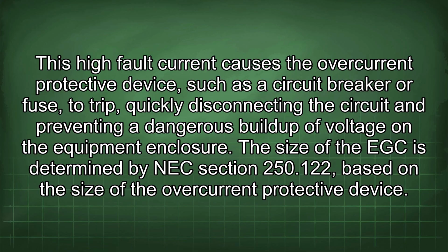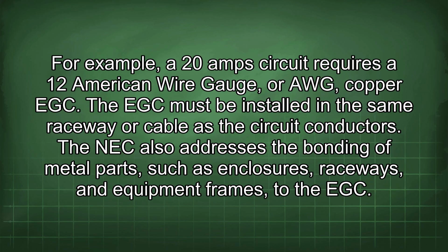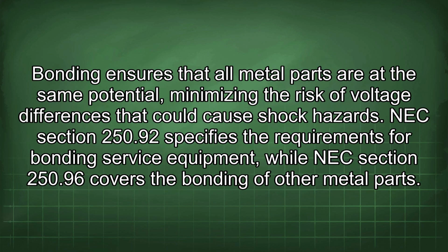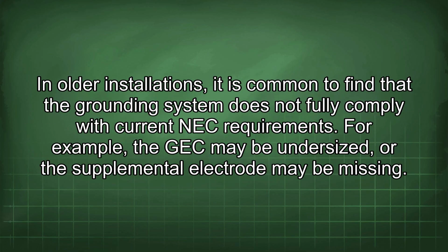The size of the EGC is determined by NEC Section 250.122, based on the size of the overcurrent protective device. For example, a 20-amp circuit requires a 12 American wire gauge, or AWG, copper EGC. The EGC must be installed in the same raceway or cable as the circuit conductors. The NEC also addresses the bonding of metal parts such as enclosures, raceways, and equipment frames to the EGC. Bonding ensures that all metal parts are at the same potential, minimizing the risk of voltage differences that could cause shock hazards. NEC Section 250.92 specifies the requirements for bonding service equipment, while NEC Section 250.96 covers the bonding of other metal parts. In older installations, it is common to find that the grounding system does not fully comply with current NEC requirements.